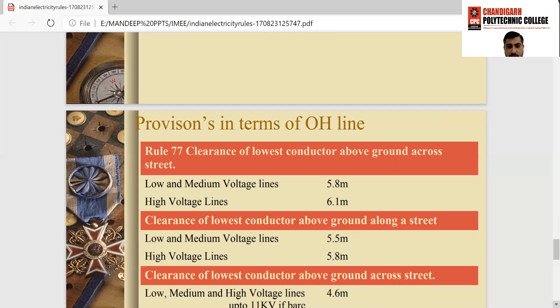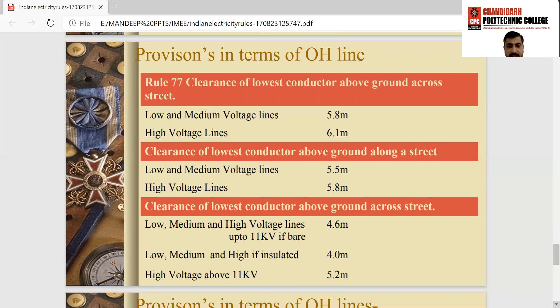The clearance of lowest conductor above ground across street for low, medium and high voltage lines up to 11 kV, if the conductor is bare, is 4.6 meter. If the conductor is insulated, for low, medium and high voltage, the minimum clearance above ground across street required is 4 meter. And for high voltage lines beyond 11 kV, the minimum clearance above ground across street required is 5.2 meter. These are some rules for provisions in terms of overhead lines.